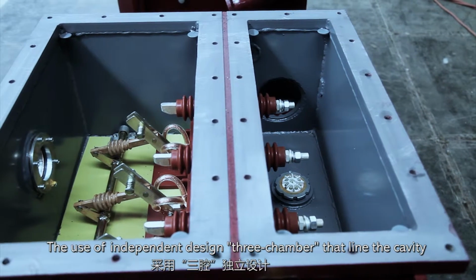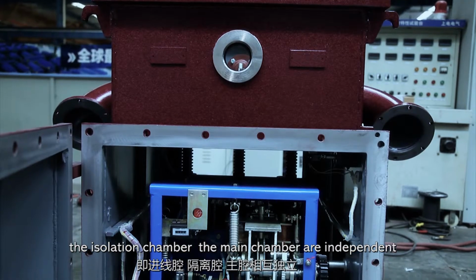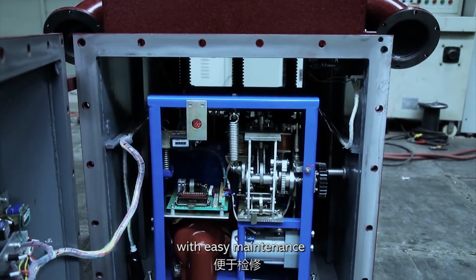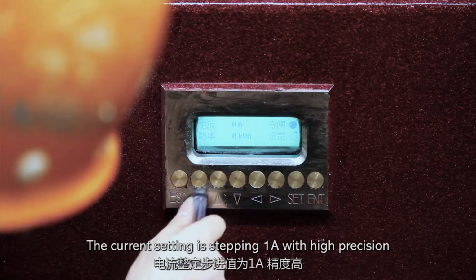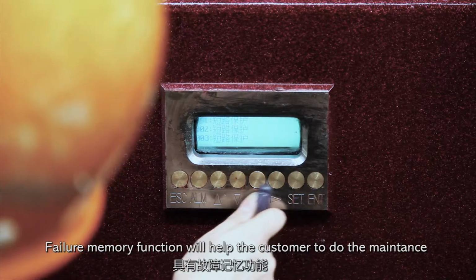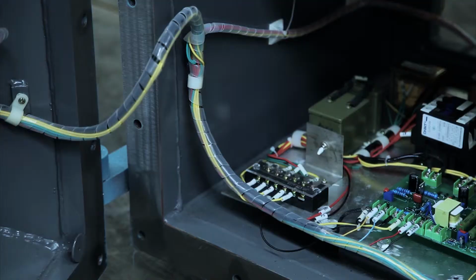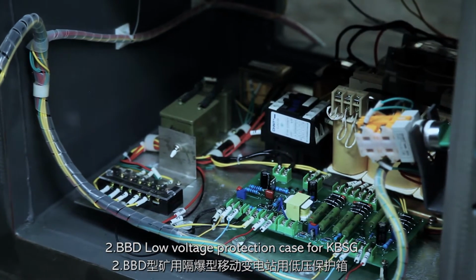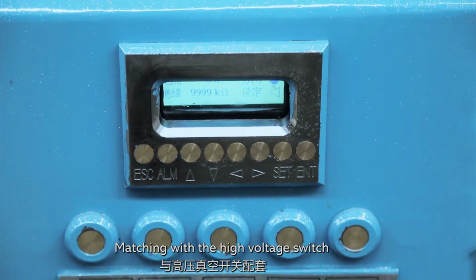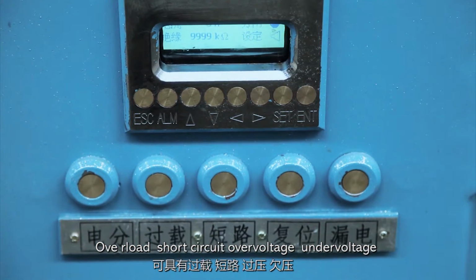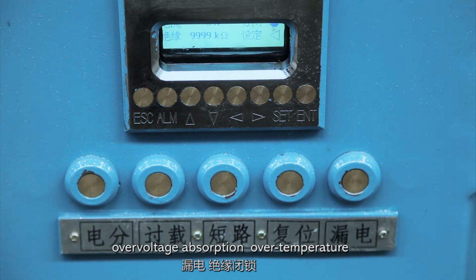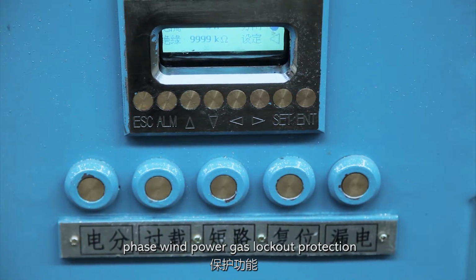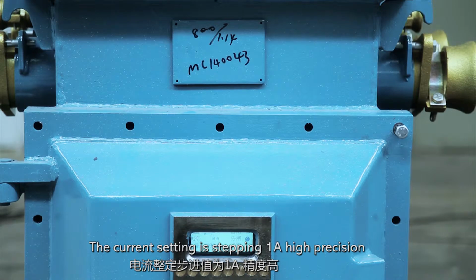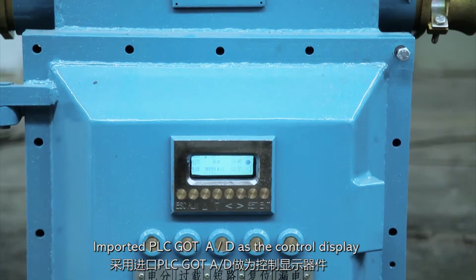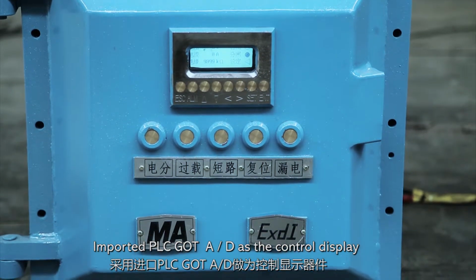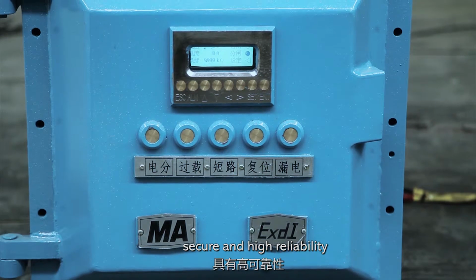It uses an independent design of 3 chambers: the line cavity, the isolation chamber, and the main chamber are independent for easy maintenance. The current setting steps by 1 amp with high precision. The failure memory function will help the customer do maintenance. 2. BBD low voltage protection case for KBSG. Matching with the high voltage switch, it provides overload, short circuit, overvoltage, undervoltage, overvoltage absorption, over temperature, phase, wind power gas lockout protection. The current setting steps by 1 amp with high precision. Imported PLC, GOT, AD are used for control and display, stable, secure, and highly reliable.